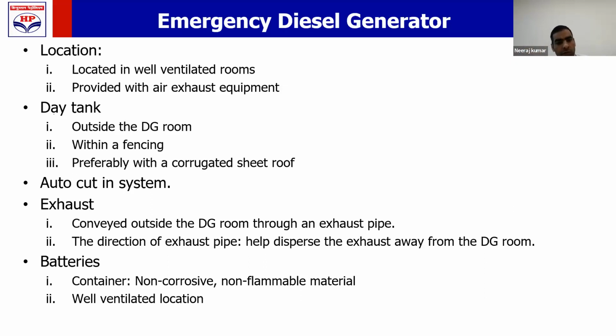If the DG is kept inside the room, then its exhaust will fill the entire room. That will not be the case. The exhaust of the DG room is conveyed outside the DG room by an exhaust pipe. You take a pipe, take the exhaust outside the room. Now, where to take that outside? Near the gate or opposite of the gate, or wind direction, or how?